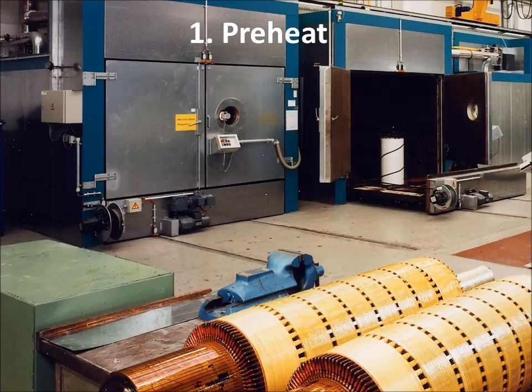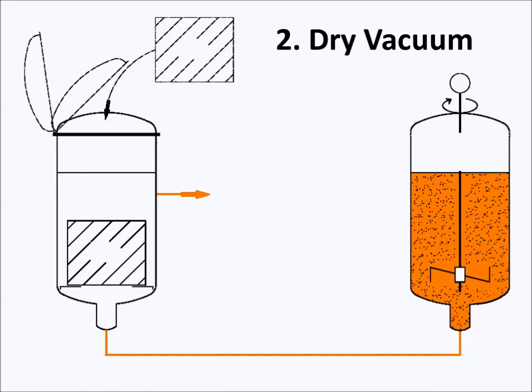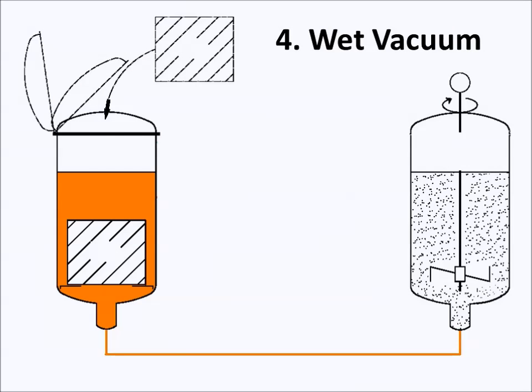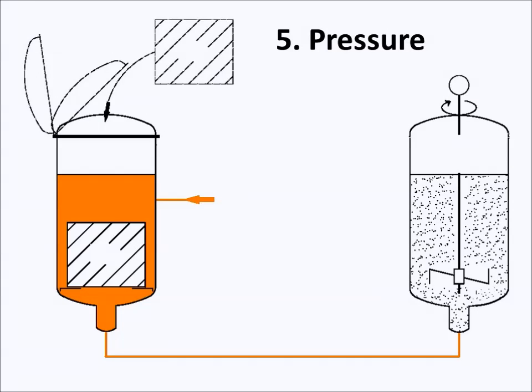The vacuum pressure impregnation process consists of several steps. First, the part is placed in an oven and preheated in order to evaporate any moisture and improve resin penetration. A dry vacuum is then applied to remove air and any remaining moisture. The resin is introduced into the chamber from the bottom up and fills in the gaps in the material. A wet vacuum is then applied and kept at this level for a certain amount of time. Finally, through the use of dry air, nitrogen, or other gases, pressure is applied to the chamber to further increase penetration.